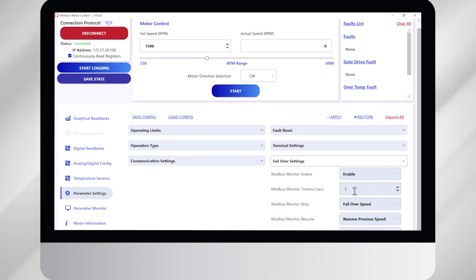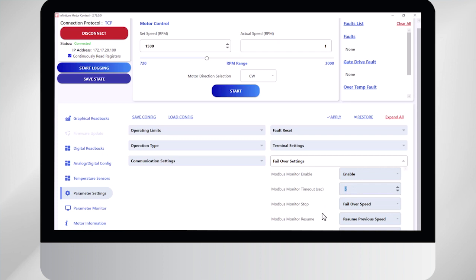The first box tells the motor how long should it wait before it goes into failover mode. In the event it loses communication, I've got it set to five seconds. So after five seconds, it's going to do this new feature that I've selected in failover mode.